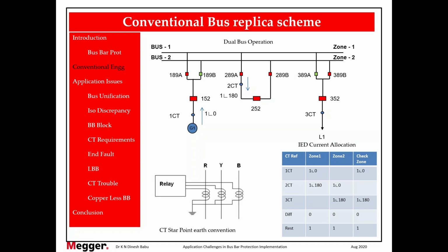So in the current scenario, you need not use multiple cores with different neutral earthing. In numerical, low impedance relays, this is possible. But if you are using high impedance, you have to go with the conventional method of having different earthing to balance the current. Next, what is the 3 CT condition?